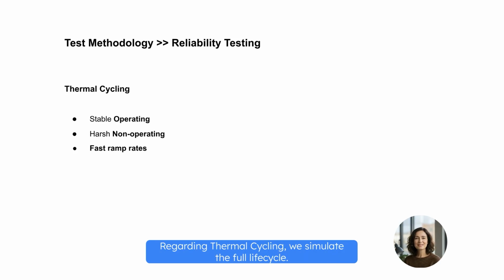Regarding thermal cycling, we simulate the full life cycle. This means validating both the stable operating range and the harsh non-operating shipping conditions, where we use fast ramp rates to really stress the materials. The failure mode here is deformation. Therefore, the protocol is strict. Immediately after cycling, you must execute a pressure test. We need to confirm that all that expansion and contraction didn't crack a seal.